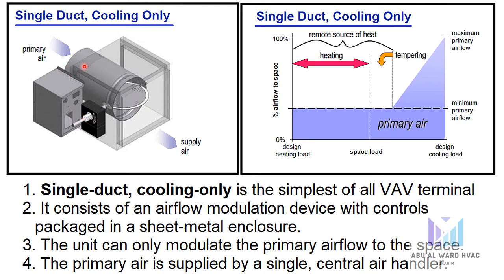The unit can only modulate the primary airflow to the space. The primary air is supplied by a single central air handler. This graph indicates how the air supplied to the space by the terminal unit varies as the space load changes. The vertical axis indicates the total airflow supplied to the space; the horizontal axis indicates the space load. The supply airflow to the space is reduced as the cooling load decreases. Responding to the space thermostat, the primary airflow is modulated between maximum and minimum settings. The maximum setting is determined by the design cooling load of the space, and the minimum setting is manually determined by the space ventilation requirement or minimum airflow for proper diffuser selection.